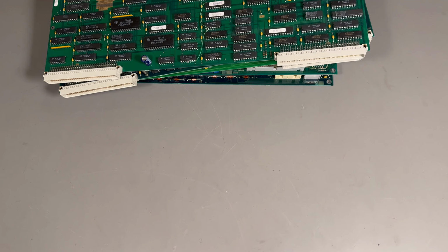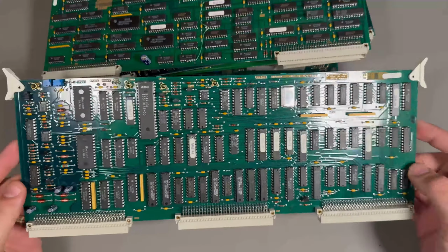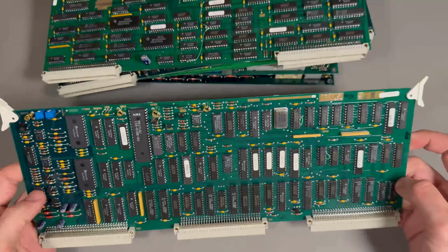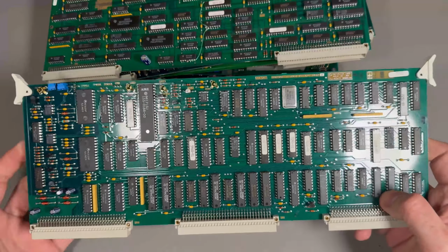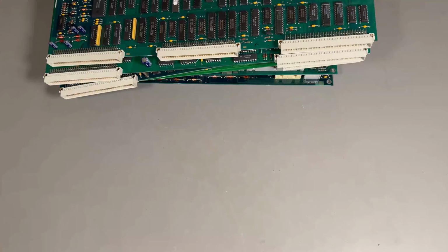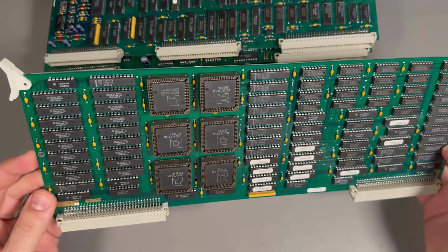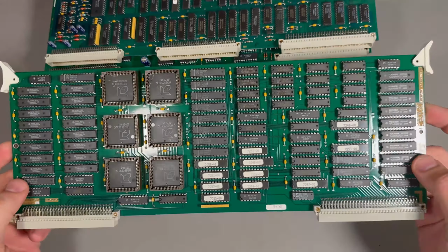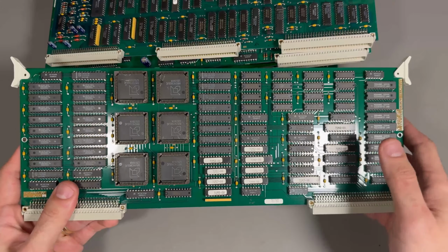And we have two more boards here. One of them is control, so I think this board just does control stuff. It helps the CPU, digital interface to the rest of the instrument and stuff like that. And this is RAM. This is the memory acquisition. So you don't need very fast memory for this thing, and it only has 1024 points of maximum acquisition window.